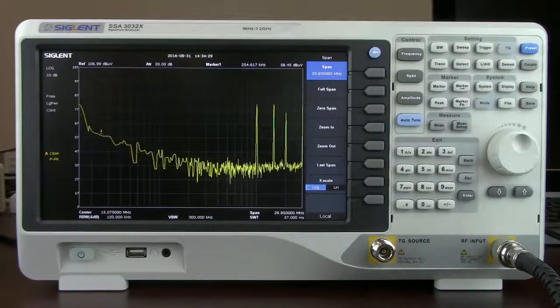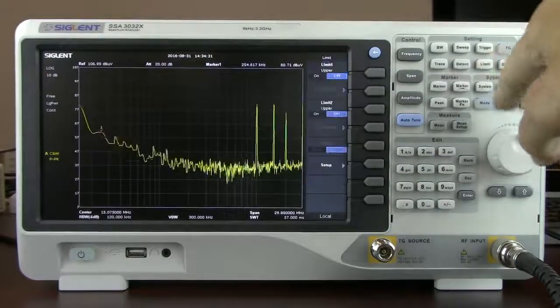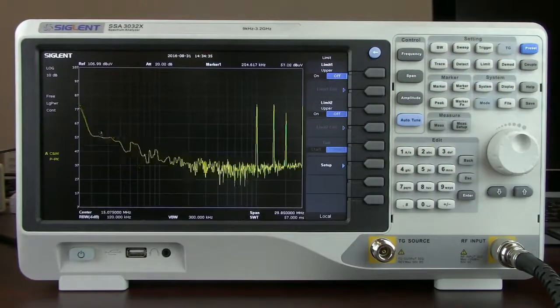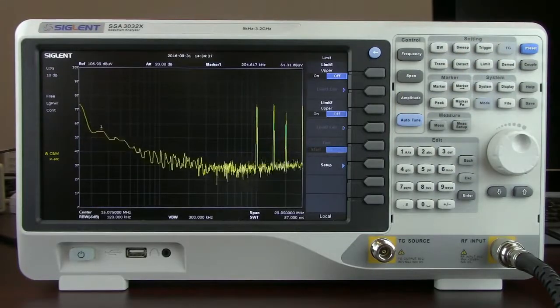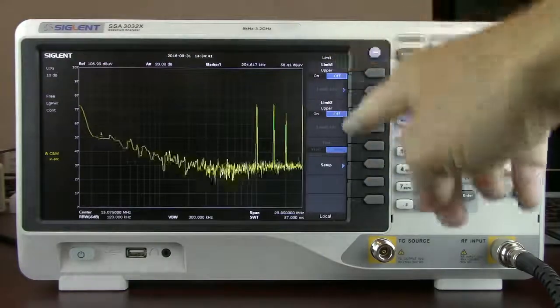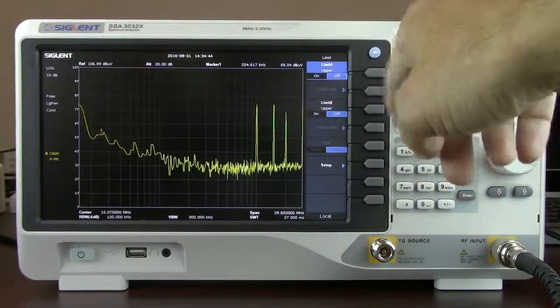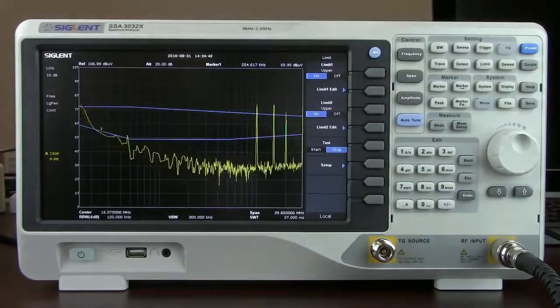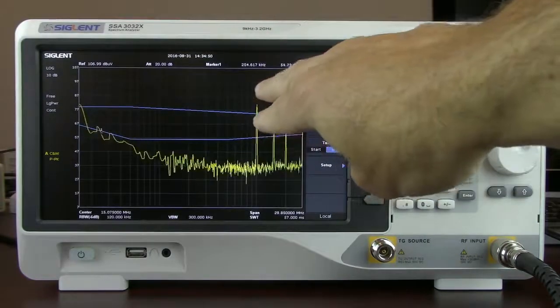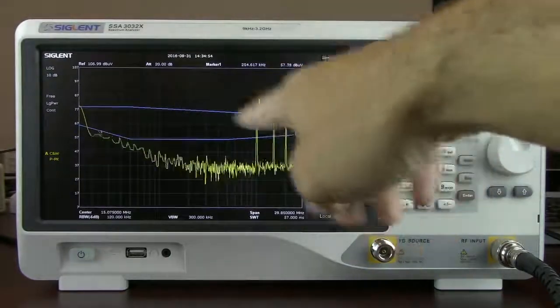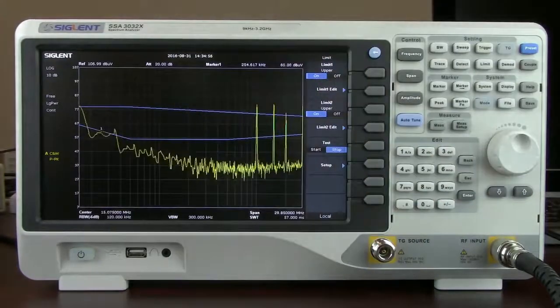And now we can enable limits. Pressing the limit key, we've got two limit lines. Many spectrum analyzers will not have two full limit lines. In this case, we've got two limit lines that we can select to be upper or lower. We'll turn on limit line 1 and turn on limit line 2. Now we can visualize the two limit lines that we need to meet or may need to meet for this particular application, and our electromagnetic performance of our device under test shown under the yellow trace here.